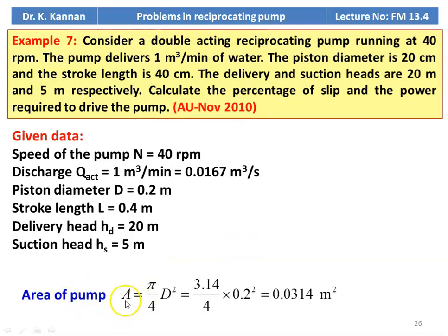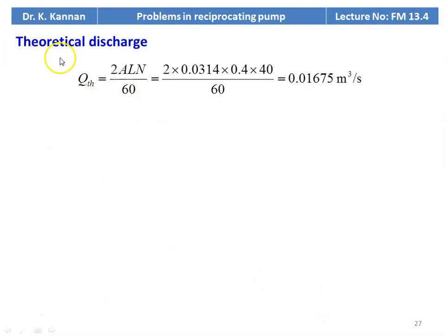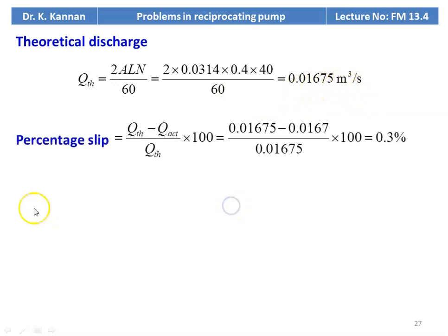Area of the pump: A = π/4 × D² = 3.14/4 × 0.2² = 0.0314 meter square. Theoretical discharge Q_theoretical = 2ALN/60 (the 2 stands for double acting) = 2 × 0.0314 × 0.4 × 40/60 = 0.01675 meter cube per second. Percentage of slip = (Q_theoretical − Q_actual) / Q_theoretical × 100 = (0.01675 − 0.0167) / 0.01675 × 100 = 0.3%.